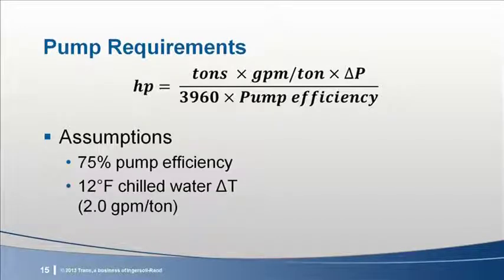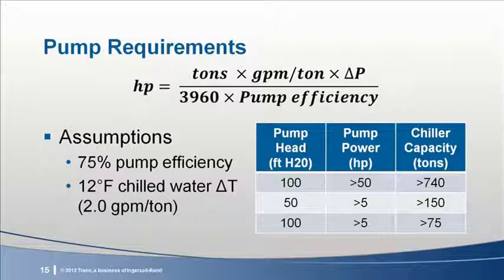For this example, we've assumed 75% pump efficiency and 2 GPM per ton, which is a 12-degree chilled water delta T. Through 2007, a VFD was not required on chilled water pumps until the chilled water capacity satisfied by that pump was 740 tons, and then only if both the pump head and power limits were met. The 2010 version brought that down to about 150 tons. But as you can see, the capacity threshold is dependent on the system pressure drop.